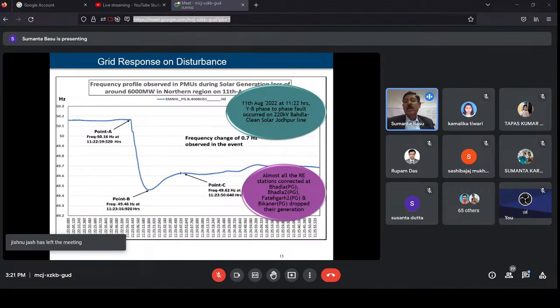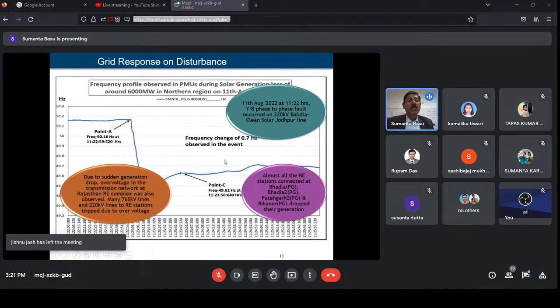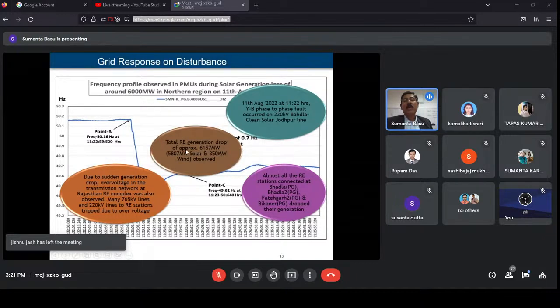So they dropped their solar energy, their generation. The third effect, due to this sudden generation drop, was over voltage in the transmission network at the Rajasthan Renewable Energy Complex, and many 765 kV lines and 220 kV lines to RE stations tripped due to over voltage. It led to a total RE generation drop of approximately 6157 megawatt, out of which 5,800 megawatt was solar and 350 megawatt wind.